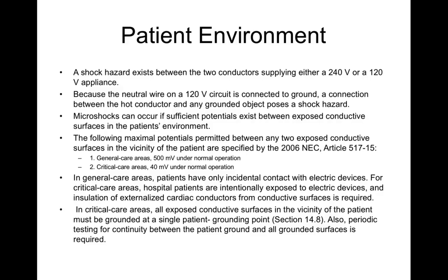And so there are some maximum potentials that are permitted according to the National Electric Code. In general care areas, the maximum potential permitted between any two exposed conductive surfaces would be 500 millivolts and under. In critical care areas, it would be 40 millivolts under normal operation.